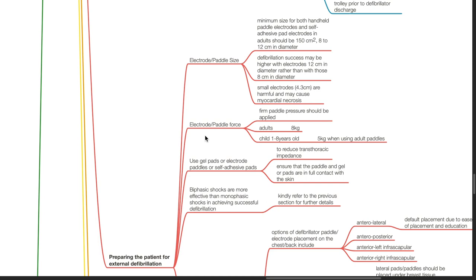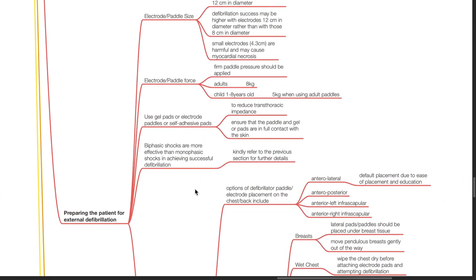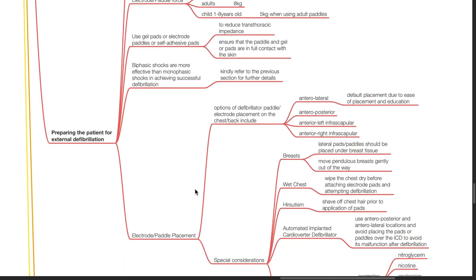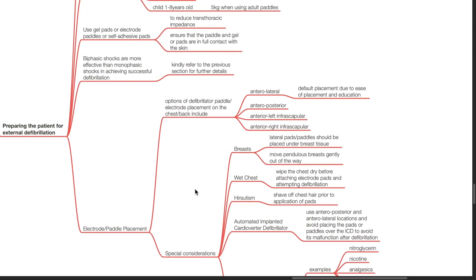Use gel pads, electrode paddles, or self-adhesive pads to reduce transthoracic impedance. Ensure the paddle and gel or pads are in full contact with the skin. Electrode or paddle placement options include anterior-lateral, anterior-posterior, anterior left infrascapular, and anterior right infrascapular.